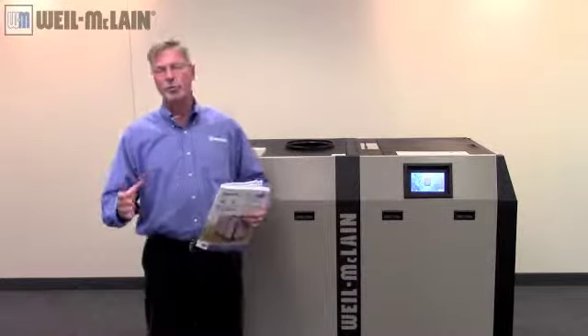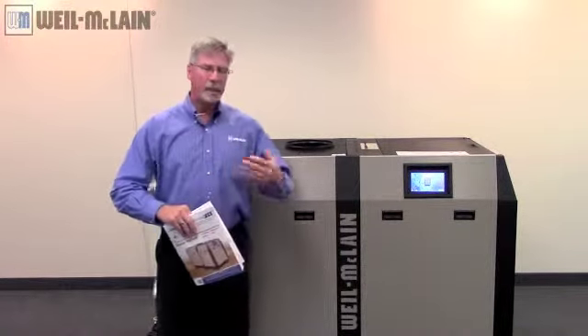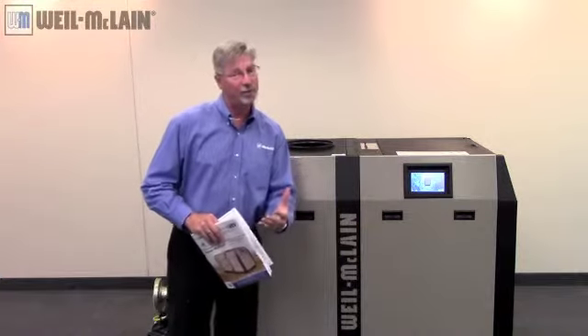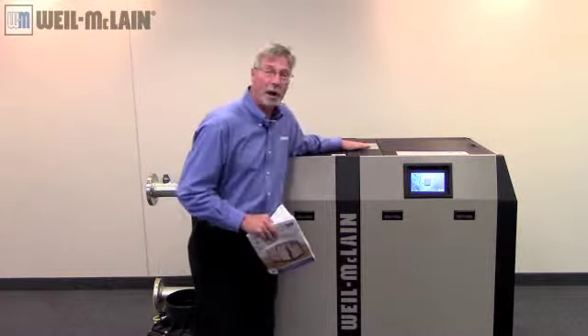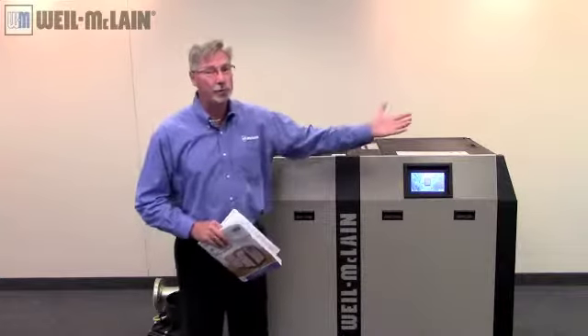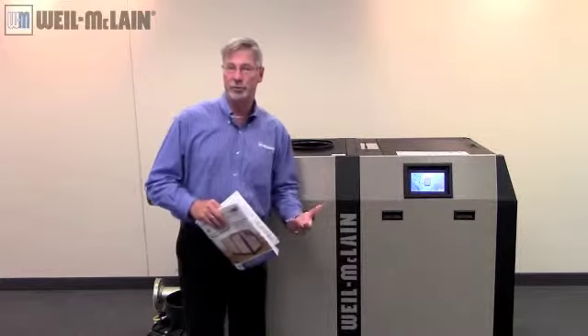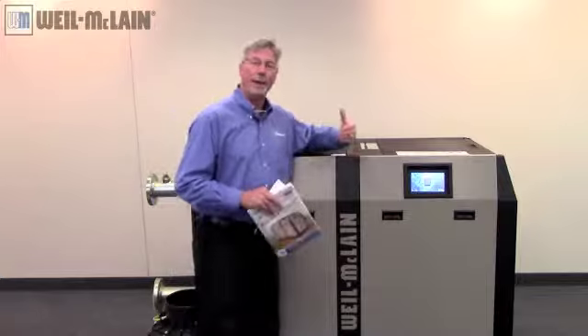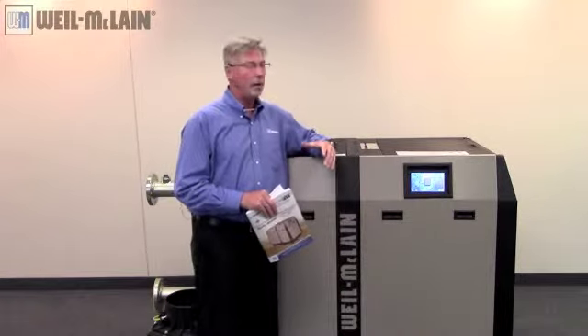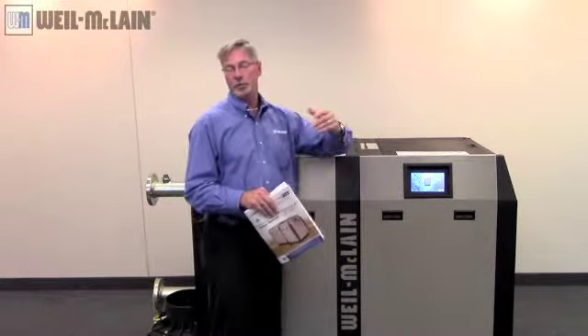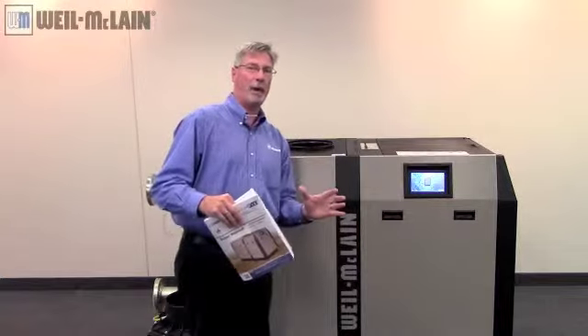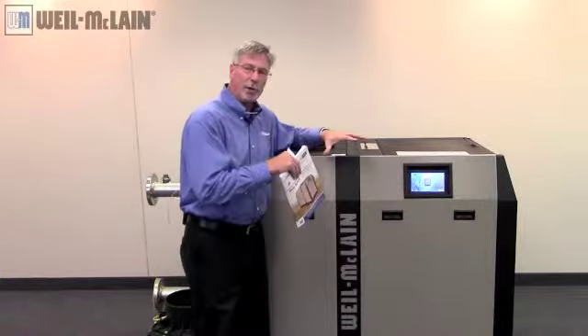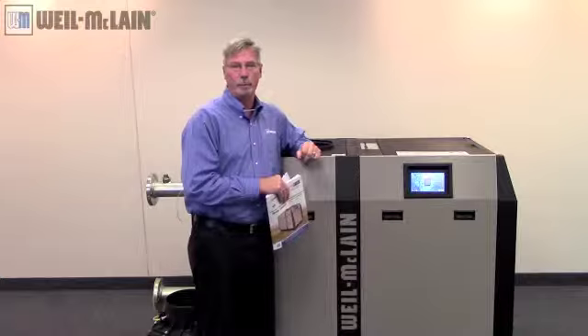And basic troubleshooting, you have to remember, guys, a lot of times we forget to check the very basics, like is the switch turned on? Is the main circuit breaker tripped? So let's do our due diligence and be sure that we've checked all the basics, all the silly things first, making sure there's a call for heat and those things like that. So once we've gotten that out of the way, now we need to get down and dirty and see what's going on with this boiler.